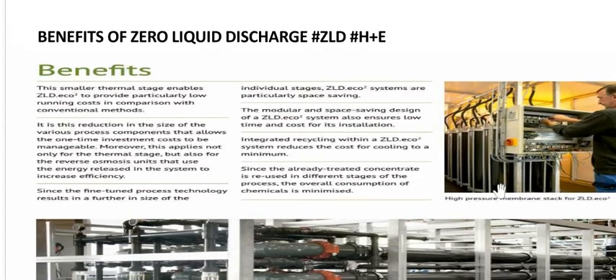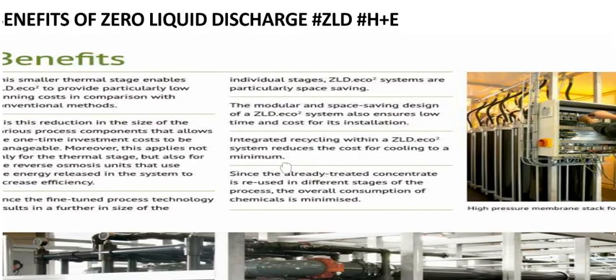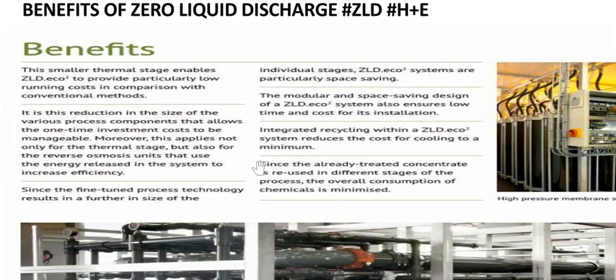Benefits of zero liquid discharge as ZLD of H+E. This smaller thermal stage enables ZLD ECO to provide particularly low running costs in comparison with conventional methods. It is the reduction in the size of the various process components that allows the one-time investment cost to be manageable. Moreover, this applies not only for the thermal stage, but also for the reverse osmosis units that use the energy released in the system to increase efficiency.